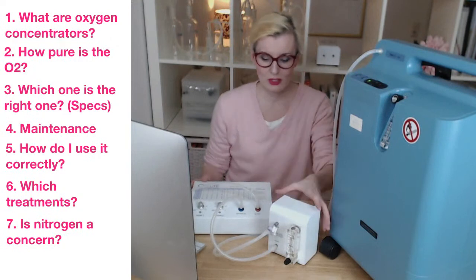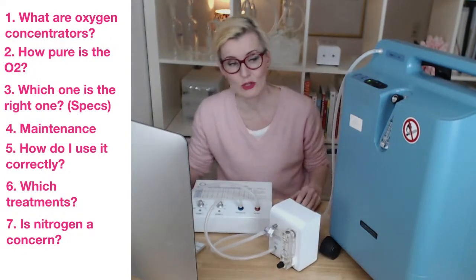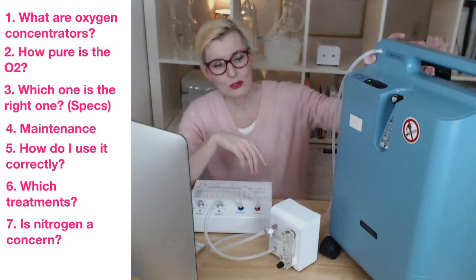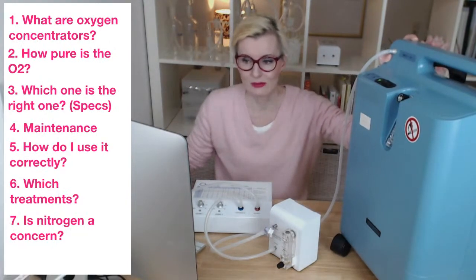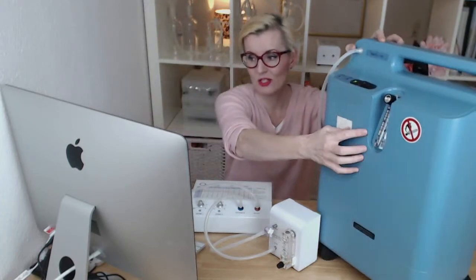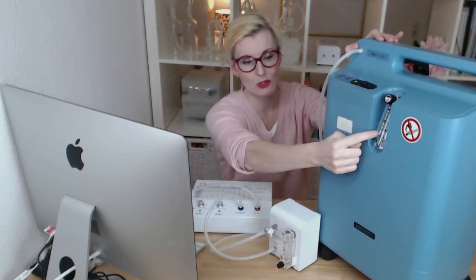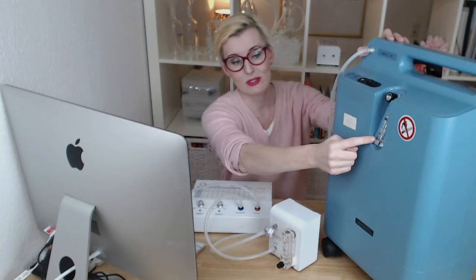Okay, so this would be a setup for an oxygen concentrator. Now, sometimes you can get extremely lucky and find oxygen concentrators already with a built-in low flow regulator. So instead of saying 0 to 5 liters per minute or 0 to 10 liters per minute, it will say 0 to 1 liter per minute. If you find such a machine, then go for it, buy it, definitely. If it works well, if it has around 5,000 hours on it or less, go and get it.